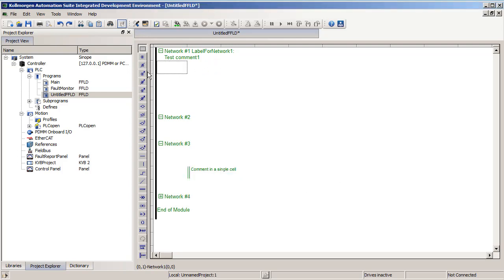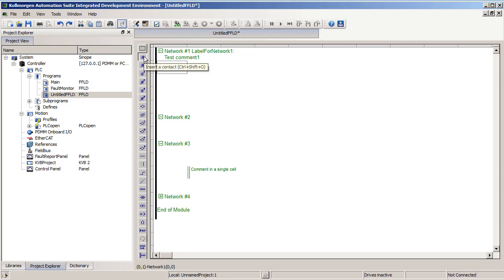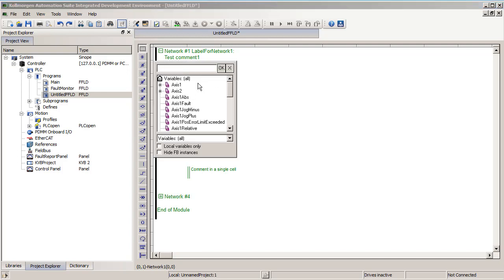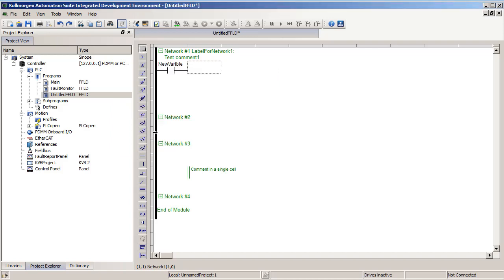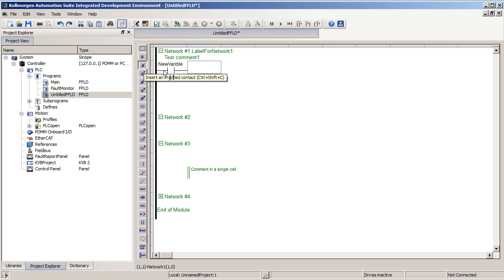We have six different contacts and six different coils to add to our ladder diagram programs. To add them, you can first select the button of the type that you want. First, I'm going to add just the standard or normally open contact. Once that button is selected, you can click on any cell in the editor to drop or place it. It will pop up with a list of all the Boolean variables that you can map to that contact or coil. Or you can start typing a new variable name. If I hit enter, it will pop up and allow you to declare this variable right from the ladder editor. So you don't have to do it separately in the dictionary.